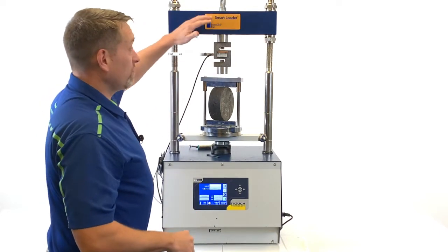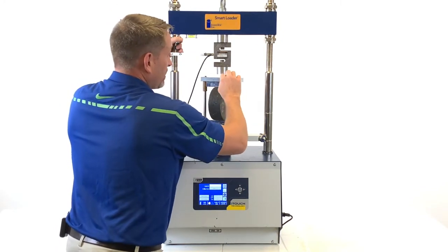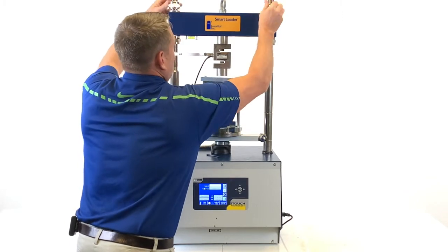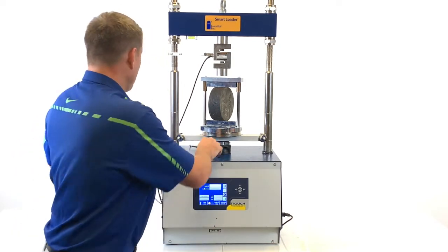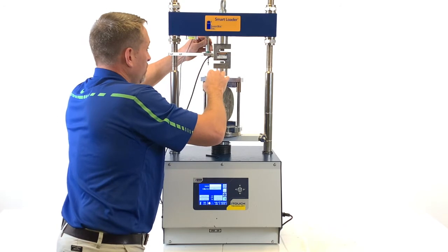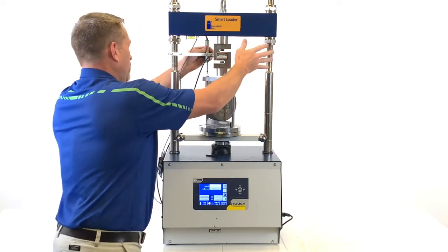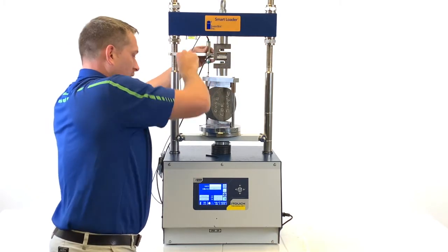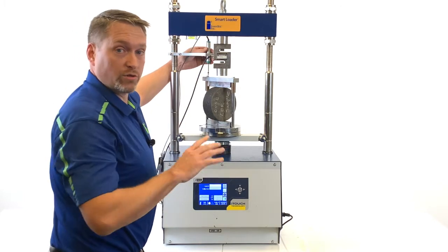It's important that the center of the Lottman head and the bottom of the load cell are in alignment as well. You may need to lower or raise your crosshead for the alignment to work out — we're looking for about an eighth of an inch between the bottom of the load cell and the top of the Lottman head. There is also an included level to make sure that the load frame is level. Once this is completed, we're going to install the LVDT. Take your LVDT, which is included, using the mounting bracket, and bring it down until it is about resting on the left post of the Lottman head. Then use your Allen wrench to tighten the screws and hand-tighten the screws on your LVDT. Once in position, make sure they're real tight so there's no play in the machine.